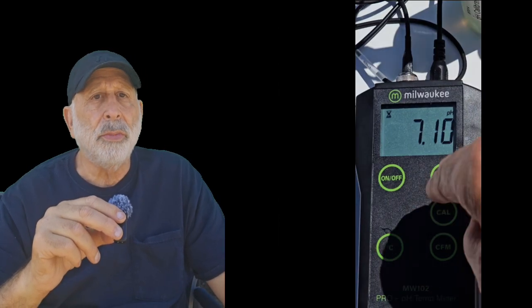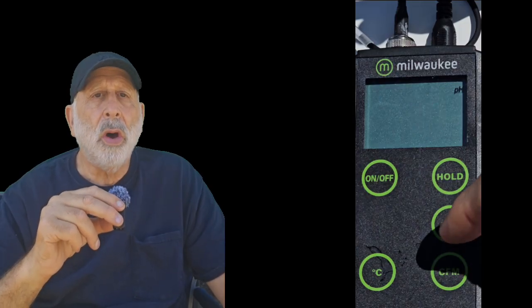Now enter calibration mode by pressing Cal. Wait until the reading stops blinking and the meter shows it's stable. Press Confirm, and at that point, calibration is complete. If you only want a 1-point calibration, you stop there.